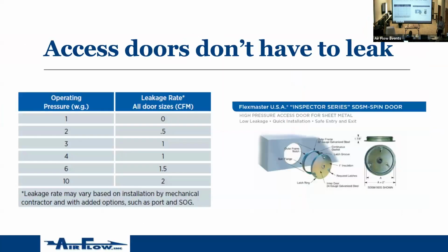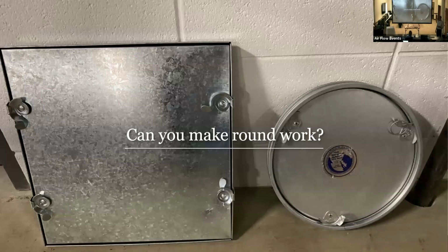This is an access door, a round one. Oh, wait, wow, that's crazy. At 4 inches, it leaks not one CFM per square, one CFM. Is this access door $100 more than, who cares? Like, specify access doors that don't leak. Do you need access doors in every job? Pretty much. Okay. Can you make it work? I'm sure the contractor is fully capable of cutting a round hole instead of a square one.